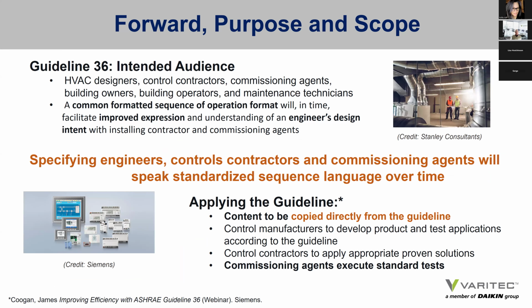Who is the intended audience? HVAC designers, control contractors, commissioning agents, and building owners. A common formatted sequence of operation will in time facilitate improved expression of the design intent. So specifying engineers, controls contractors, and commissioning agents will speak a standardized language of sequences over time that will facilitate the future of sequence writing. The guideline was written and formatted so that the sequences proposed can be directly copied and put on mechanical drawings. I saw it recently on a Smith Group project for the U of A, where they actually referenced Guideline 36 on the drawings after a scrutinized review and provided the language right on the drawings, which is part of the guideline's intent.